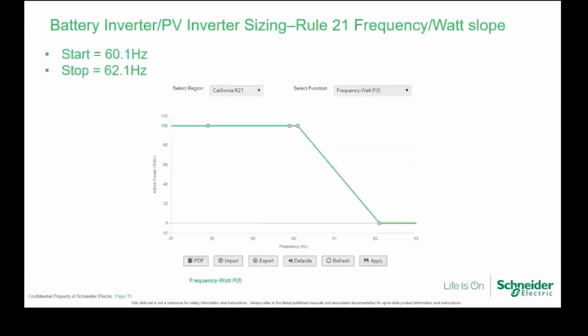It also can do a power derating itself depending on what the frequency is. For example, at 60.1 Hertz, it's fully output. At 62.1, that's when it drops off, but there's a ramp rate associated with that, so it doesn't actually just shut off. It'll slowly ramp down as the frequency increases, and go back online to full power output once the frequency reaches back down to 60. That's if you want to export.